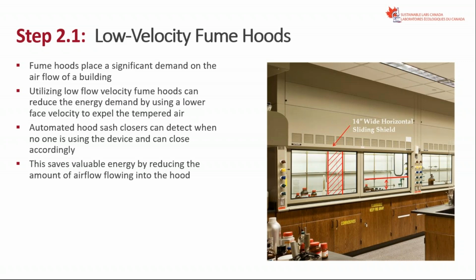California stands out with rigid requirements of 100 feet per minute so far, but in other parts of the United States and abroad, we can use low velocity fume hoods, which will reduce the velocity through the fume hood opening from 100 to 60 feet per minute. This automatically brings a reduction in energy use by 40%, because the air being exhausted from the fume hood is released outside of the building. Now it needs to be replenished, and we're going to have some heating and cooling attributed to this air being brought inside the building.